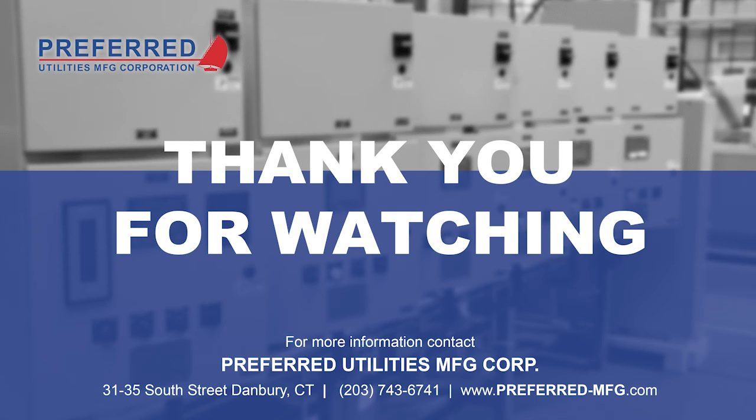Okay, next question. With different spring pressure drops available in the anti-siphon valves, how is it designed to determine which one to use? You're going to use the spring that correlates with the height of your main storage tank. So if you have a 10-foot diameter storage tank, the lowest point in your line is going to be ground level or close to it, and the top of the tank is going to be at 10 feet. Use a 10-foot spring. If your pumps are up a little higher, like on a pedestal, you might use a 5-foot spring in that application.